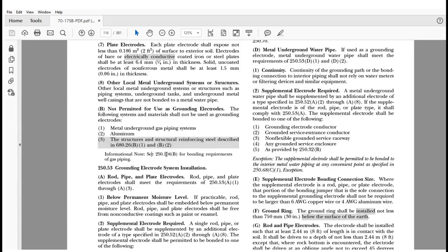All right, again, this doesn't relieve you of your requirements in 680. Please don't forget that requirement. It also reminds you, I talked about the gas piping, the informational note didn't change here, but it reminds you of bonding of gas piping, which is what I alluded to earlier. It doesn't remove you from that. We're strictly talking about what is prohibited from being used as electrodes in this application.